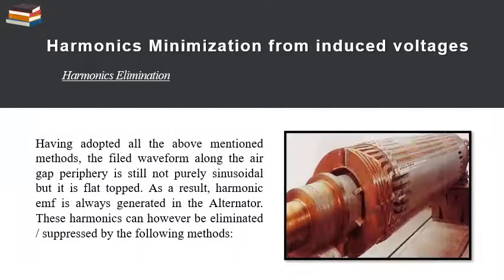Okay, so this is the diagram of the rotor for an alternator. Having adopted all the above mentioned methods, the field waveform along the air gap periphery is still not purely sinusoidal, but is flat-topped. As a result, harmonic EMF is always generated in an alternator. These harmonics can, however, be eliminated or suppressed by the following methods.